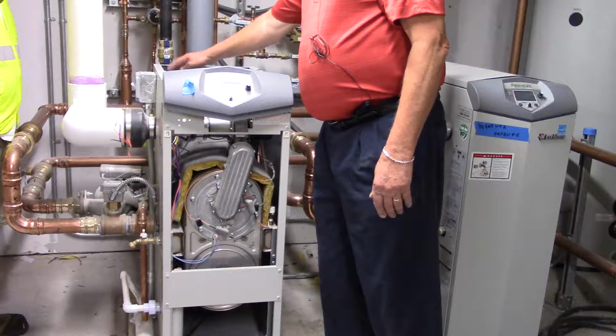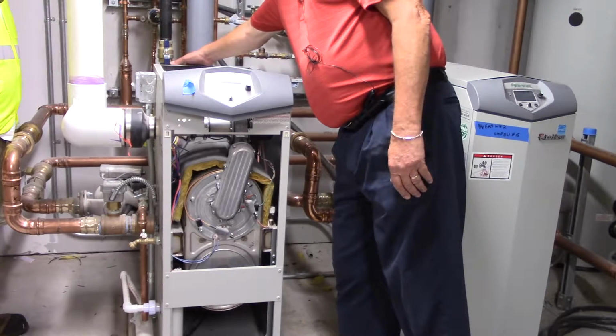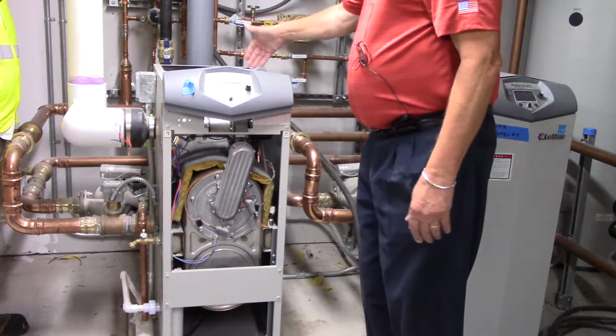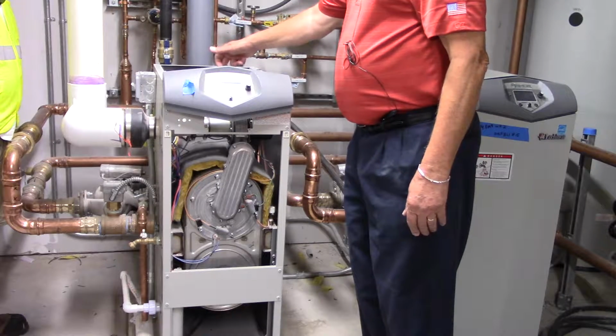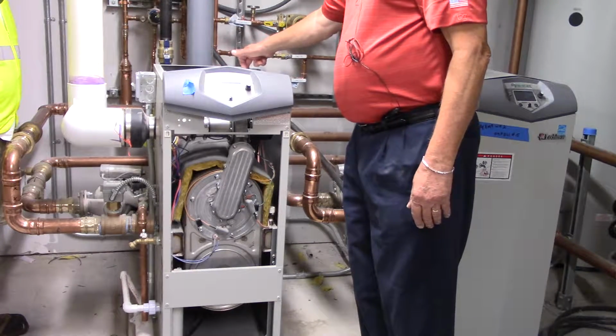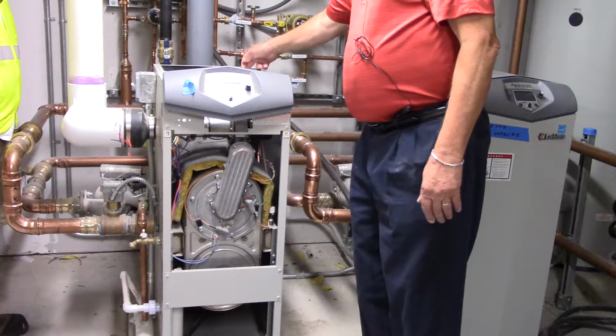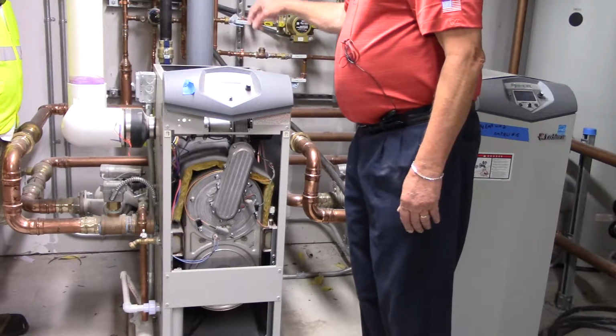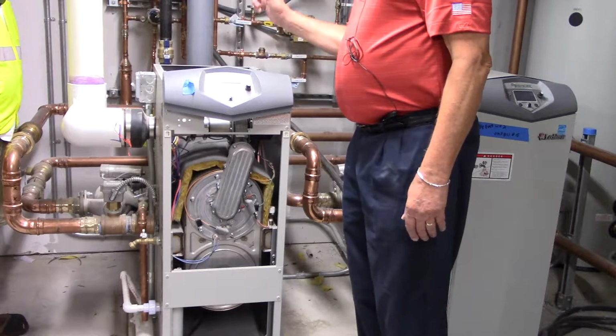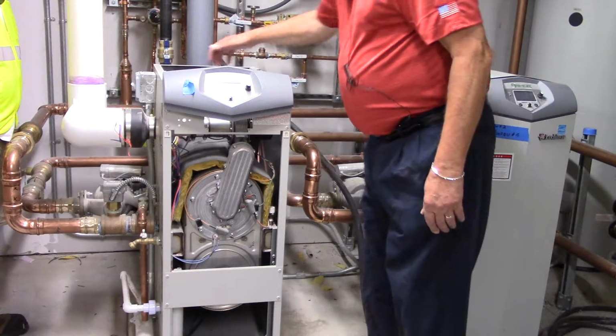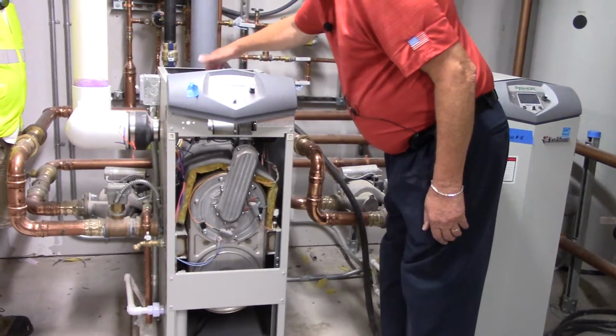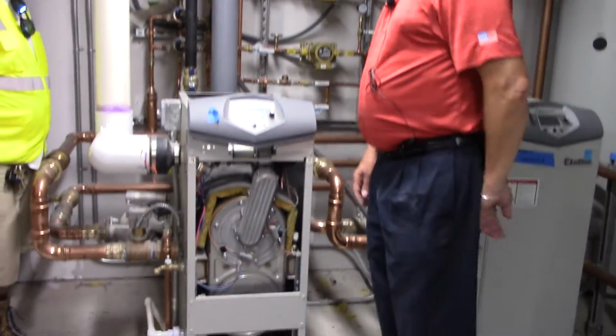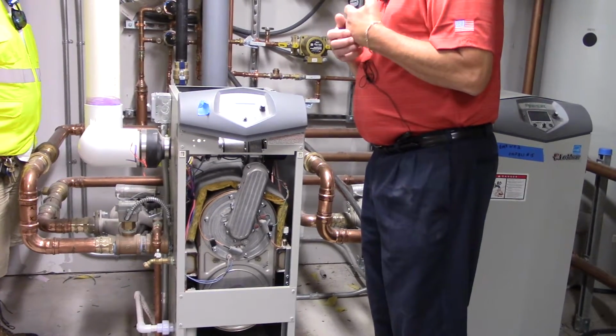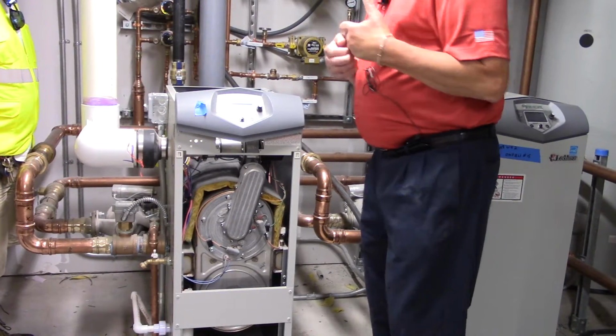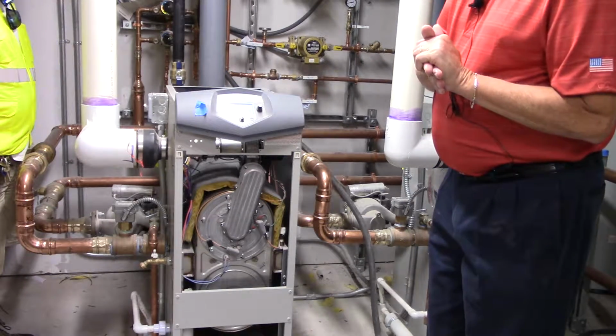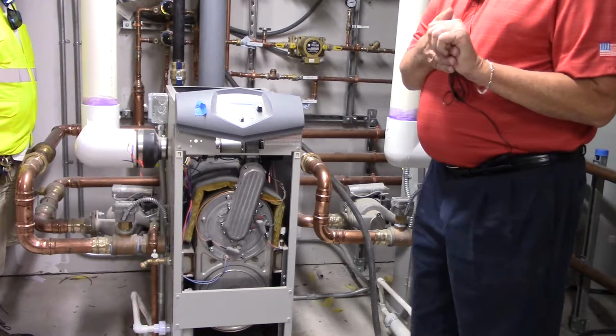All your high voltage is in here. There is a service switch on the back. This is your low voltage board. There's bus fuses, extra bus fuses. There's 3 bus fuses on the processor that's underneath this cover. To get to here, you pop this off. There's a nut on a piece of rod that comes up. You just back it off. Take these off over here and just lift it up and slide it out. That's really about all there is to it.